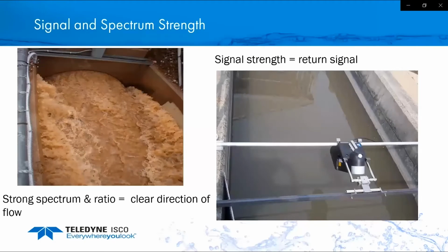So what we're looking at here on the left is that we've got a strong spectrum and ratio. What that's showing is that all that water is going one direction, and I've got a really strong return signal because there's a lot of particles in that water, and a good return signal back. Now the signal strength over here on the right, what we're looking for is a reading that's usually in the 40 to 70% range. So we've got a nice uniform flow. We're getting a nice strong signal back. And so what you're going to look at with the diagnostics on an AV sensor is more the trend. What does it start with? And it's going to be a range of, like I said, usually 40 to 70%.